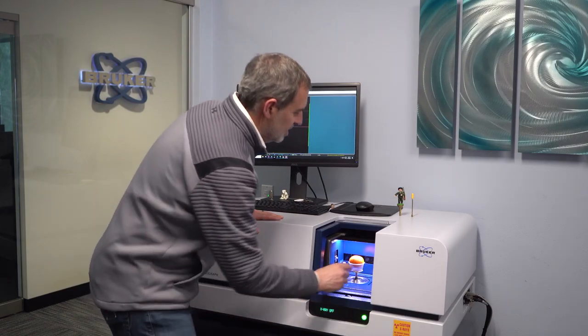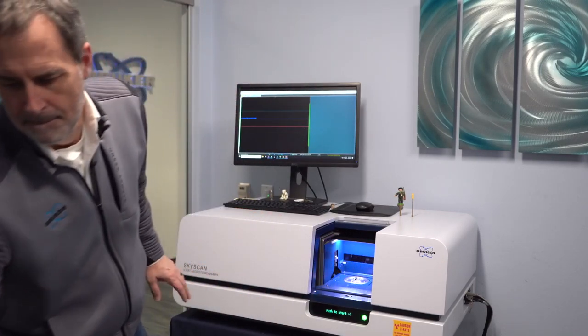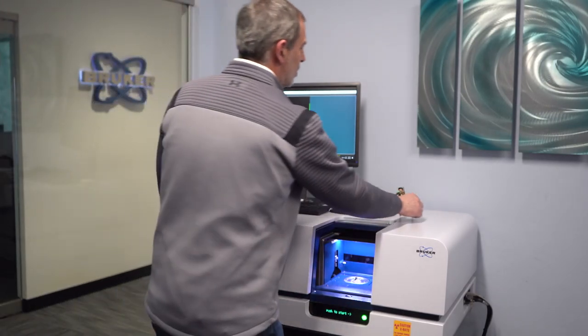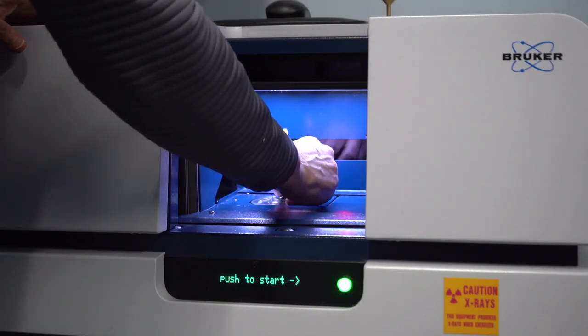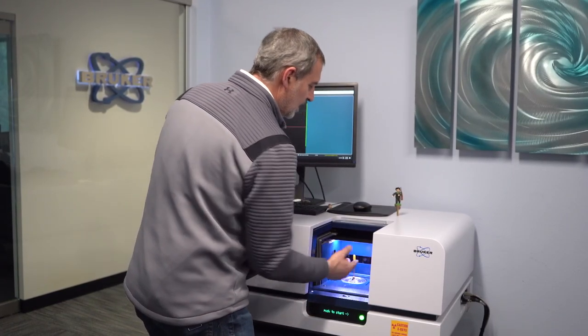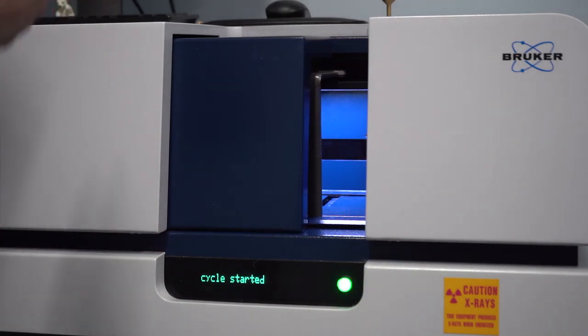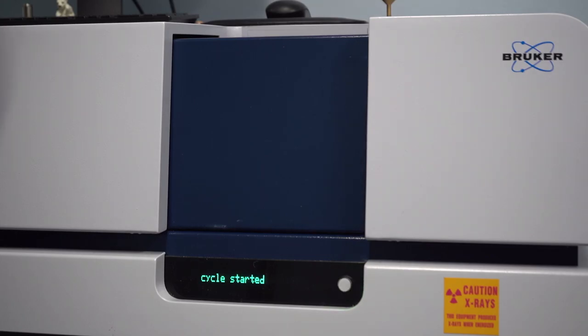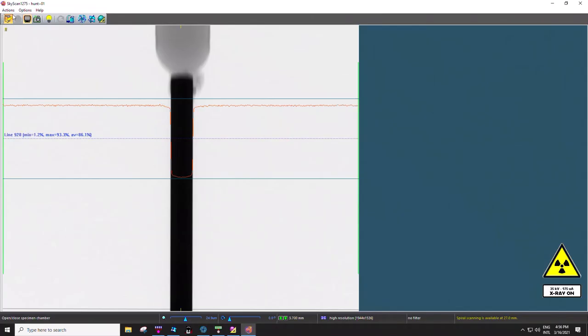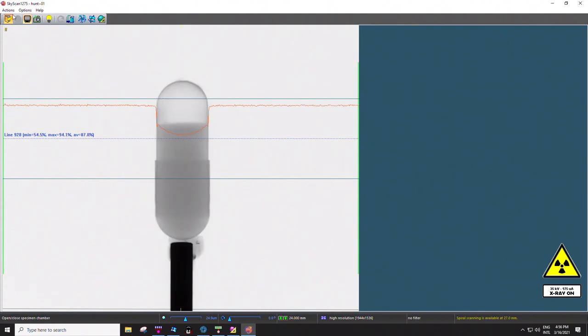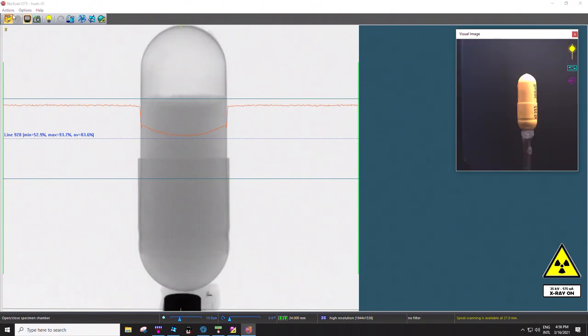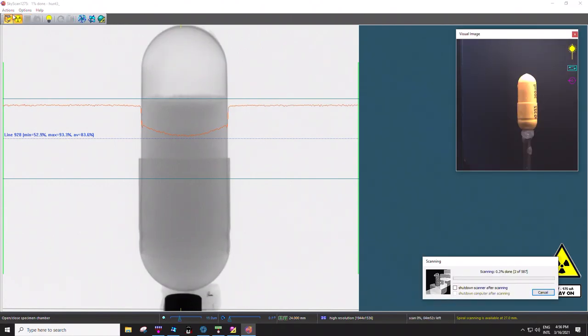It looks like John's sample is done. Let me get the orange off. The next sample I'm going to run is the pill. The pill's a great sample for push button mode — you're probably going to be running a lot of samples, it's small and pretty simple to load. In push button mode, I have all the parameters preloaded and all I have to do is hit the start button. It does everything — it closes the door, it adjusts the stage position to the exact position I wanted. I think I've set it for 12 microns, so the stage is lowering and moving towards the source. And now we're scanning. That's really all there is to push button mode.